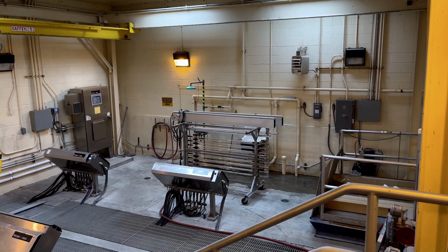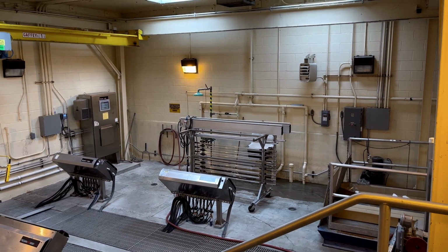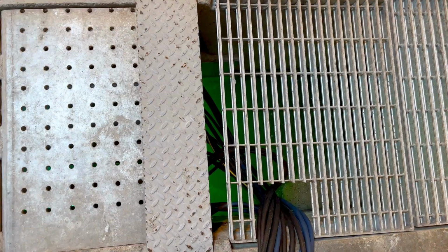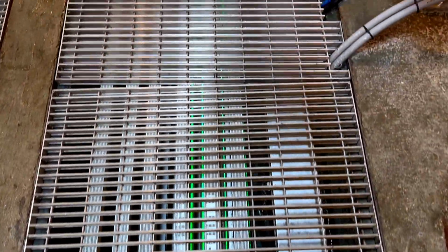In this building are banks of UV light bulbs that turn on and off or intensify as needed based on the rate of flow and clarity of water. The water is sterilized and bacteria are stopped from reproducing. This ensures that the bacteria will not multiply in the receiving stream.